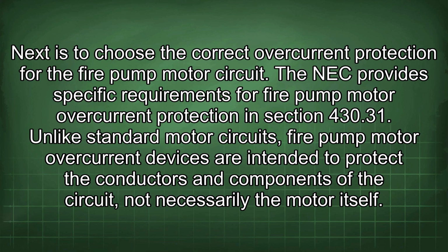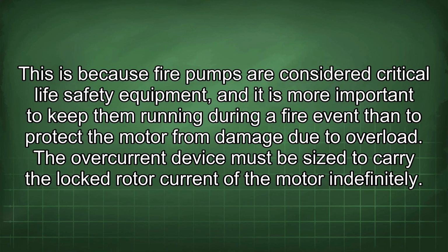The NEC provides specific requirements for fire pump motor overcurrent protection in Section 430.31. Unlike standard motor circuits, fire pump motor overcurrent devices are intended to protect the conductors and components of the circuit, not necessarily the motor itself. This is because fire pumps are considered critical life safety equipment, and it is more important to keep them running during a fire event than to protect the motor from damage due to overload. The overcurrent device must be sized to carry the locked rotor current of the motor indefinitely.